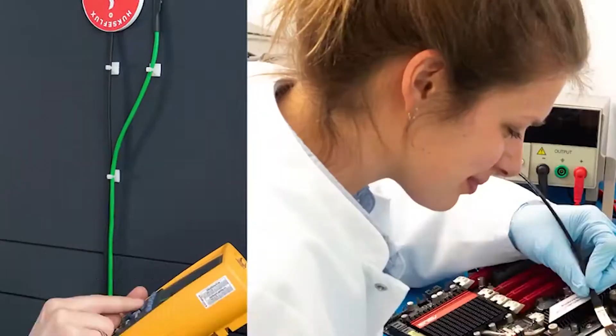This is a heat flux sensor. Inside it, you will find a very sensitive temperature difference sensor, a thermopile. A thermopile generates a voltage output signal proportional to the local heat flux, and thermopiles do not require any power supply.